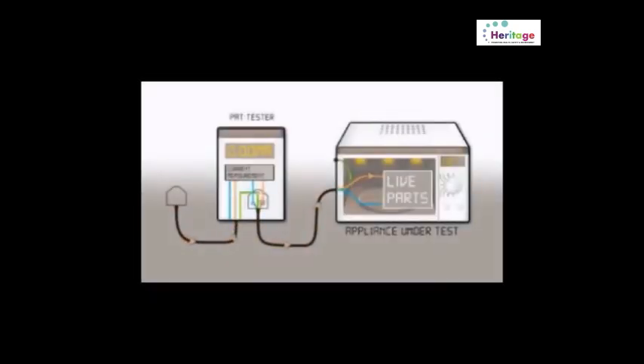To measure a protective conductor current, the appliance is plugged into the PAT. When the appliance is energized, current will flow from the main supply to the appliance in the live conductor, indicated via the brown arrow, and then return to the supply via the neutral conductor. If there is good insulation between live parts and protective earth, the live and neutral currents are equal, i.e., all of the current entering the appliance in the live conductor returns to the supply in the neutral. If there is a fault with the insulation, some of the current flowing in the live conductor will return to the supply via the protective earth. The PAT will detect this imbalance in the live and neutral currents and display the result.